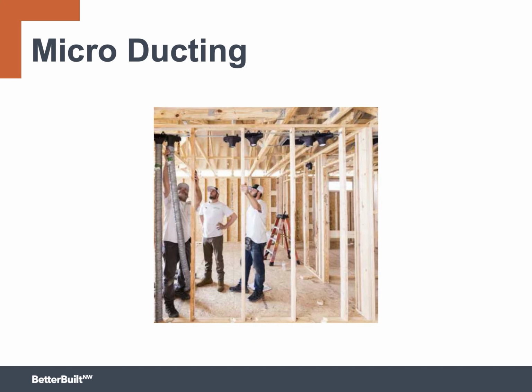Some of you may be thinking, wait, didn't they already try this in the 1980s and 90s? What happened to that idea? In those days, there were microducting systems that could move the same volume of air as a standard heating system, but do it with smaller ducts. This was accomplished by increasing the air velocity. This puts the ducts under higher pressure, which also increased duct leakage. A system operating under higher pressure also had to be designed differently. And sometimes high-velocity systems created too much air noise at the supply grills.